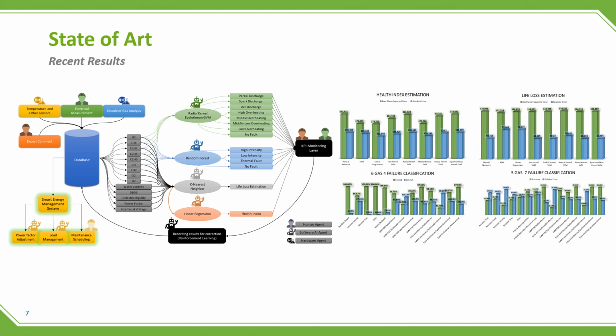Dissolved gas analysis can also classify only 2 levels of discharge and detect thermal faults by using random forest with an accuracy of 100%. However, these algorithms are highly dependent on the dataset.